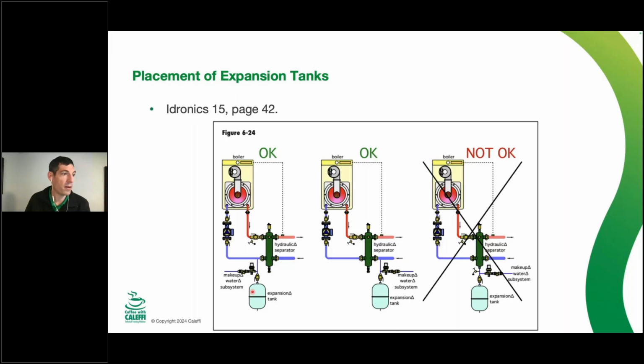The expansion tank can be in a few different spots with the hydro separator. We can do it right before the inlet of the pump, right here. That's always a great spot in any scenario to put your expansion tank, right before the inlet of the pump, so you're pumping away, like Dan Holohan has said. In a hydro separator scenario, since the pressure drop is so minimal, almost negligible right here, you could actually put the expansion tank right on the right side of this hydro separator and it would work okay.